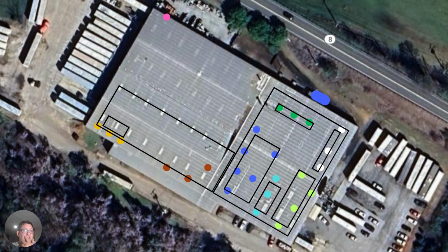Everything else was Monday through Friday. I think it was about 4 a.m. to 9 at night, Monday through Friday. These three golds actually were less than that. That was like 4 hours on a Thursday or something. But when we looked at these three green dots, they had to run 24/7. So by using the loop and subloop design, we're able to isolate out everything else and reduce a whole lot of leaks and load on the compressed air system as well.